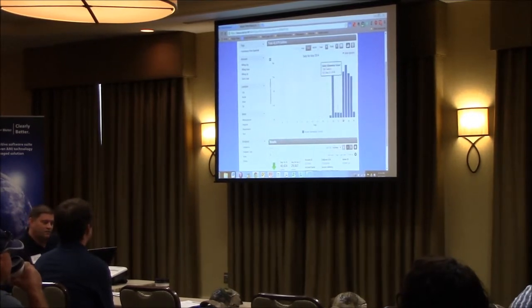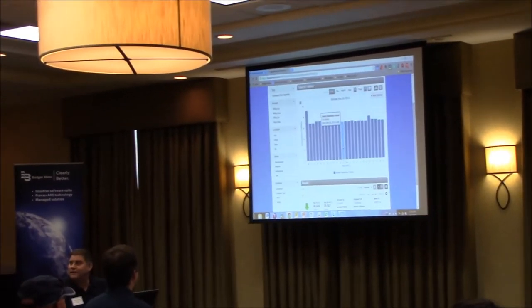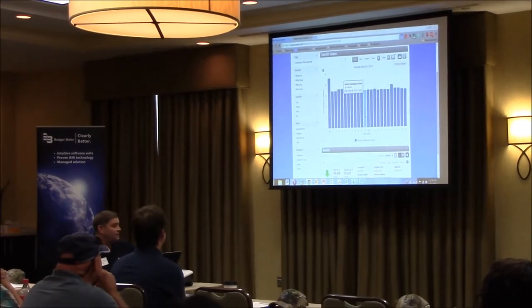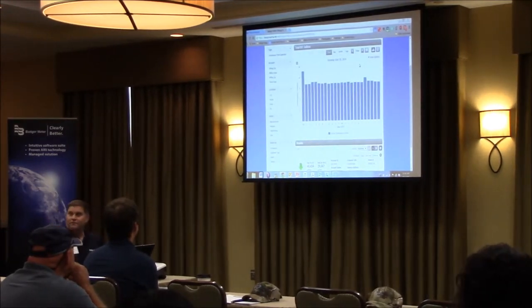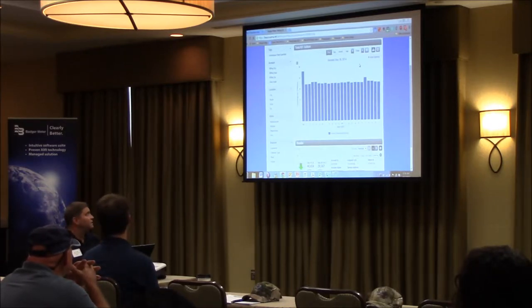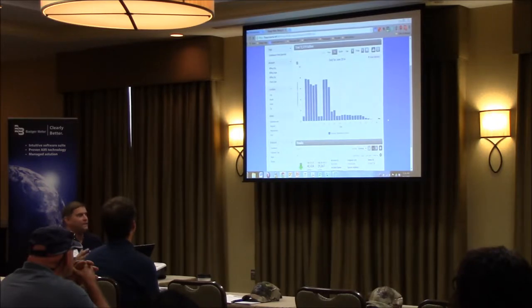830 gallons. What we look at is, if we drill into that, 34 gallons an hour going through that meter. So that's 800 gallons a day going through their meter that they're not using. That came to about $200 a month in extra water bill. We tracked it down, and you can see toward the end of June, we found it, it got fixed, and so they dropped off of that.